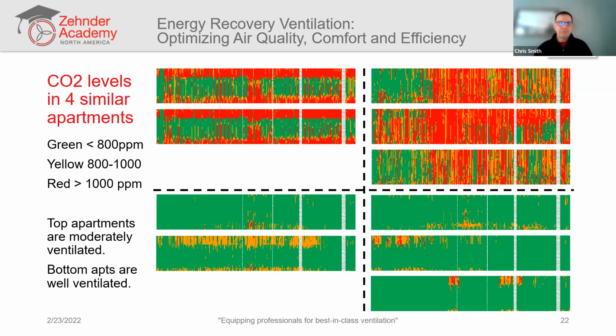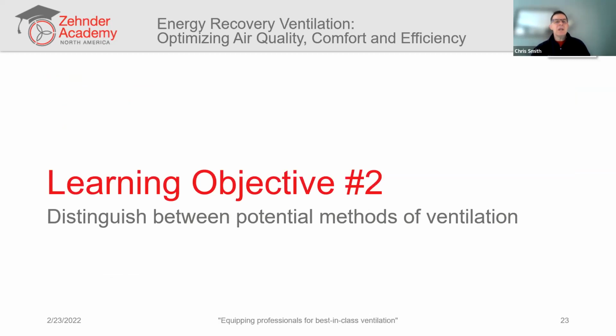And CO2 is interesting. A couple of times today we'll talk about CO2. CO2 is the easiest sort of contaminant to measure. It's what's given off as we breathe, and so it's a really good indication of occupancy. And occupancy is a pretty good indication of air quality issues. And what's been found is that if you can measure CO2 and see where its levels are, you have a pretty good representation of what the other sorts of indoor air quality contaminants are like. So that's why this is interesting. Anyway, bottom line is that a good consistent ventilation rate improves indoor air quality in a measurable way. So we've sort of associated ventilation rates with indoor air quality.